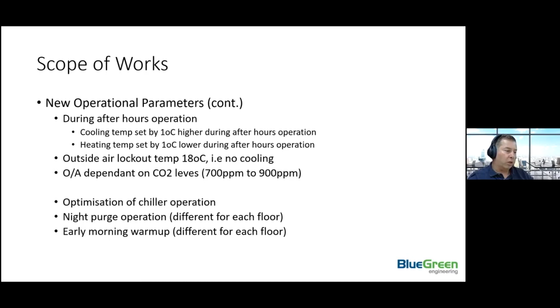Moreover, we optimized the operation of the chiller. We introduced a night purge function, whose purpose was to flush out the warm air early in the morning before cooling. And we also had an optimal warm-up procedure for winter time, which was different for each floor. Next slide, please, Stephen. During the commissioning process, we made sure that the parameters were entered by the contractor as per the design documentation and the design intent. And we made sure that those parameters were producing energy savings throughout the building and also better thermal comfort.